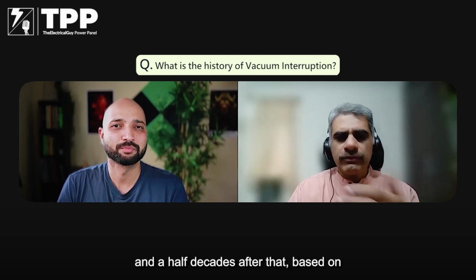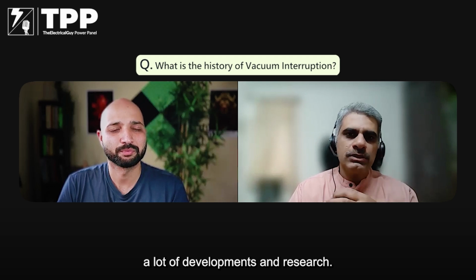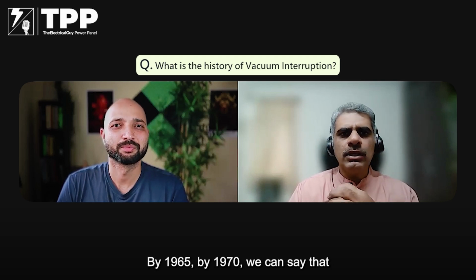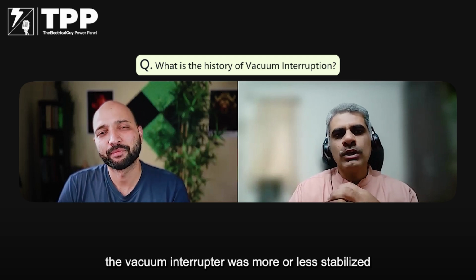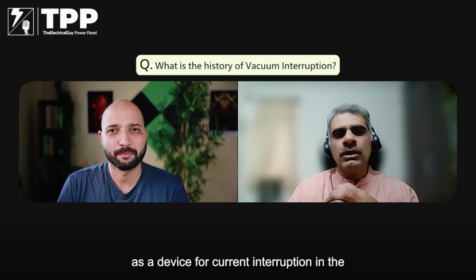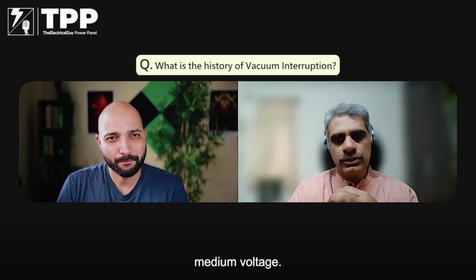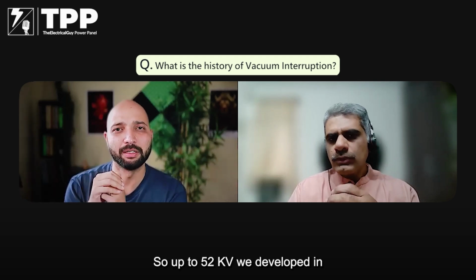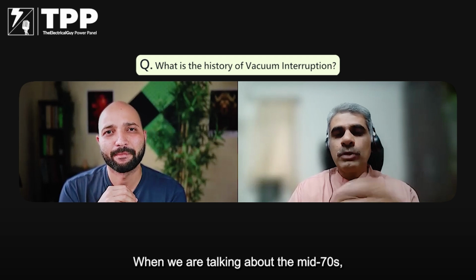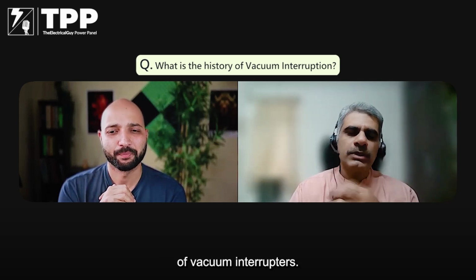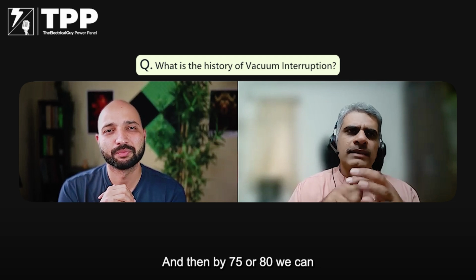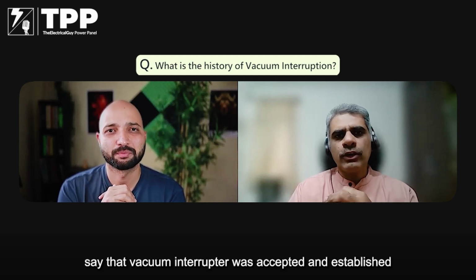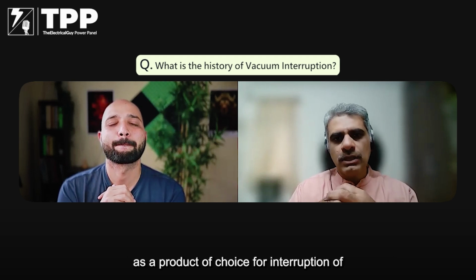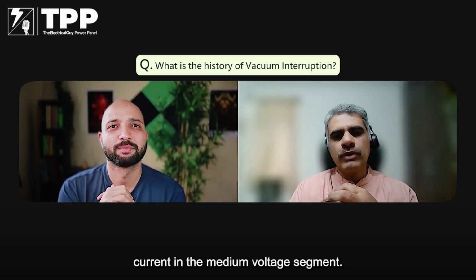Over a period of one and a half decades after that, based on a lot of developments and research, by 1965, by 1970, we can say that the vacuum interrupter was more or less stabilized as a device for current interruption in the medium voltage. Up to that time, it was 12 and 36 kV, and once we got to 1970 we developed 52 kV. Still, when we are talking about the mid 70s, it was 12, 24, 36 kV kind of vacuum interrupters. And then by 75 or 80, we can say that the vacuum interrupter was accepted and established as the product of choice for interruption of current in the medium voltage segment.